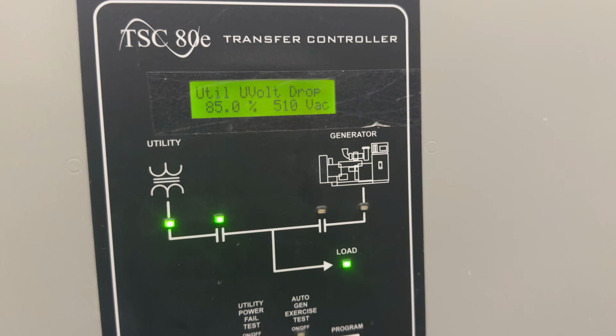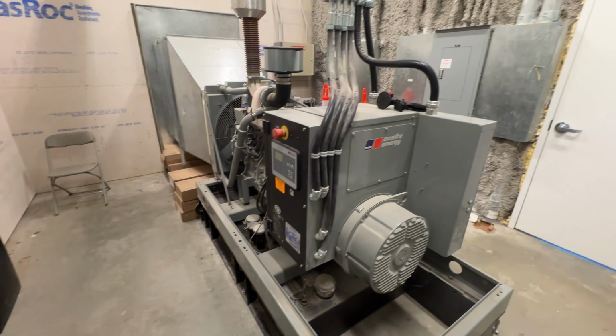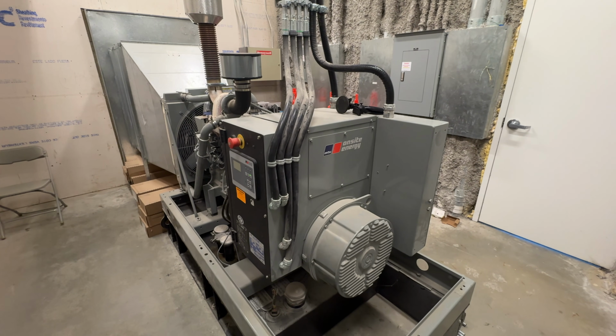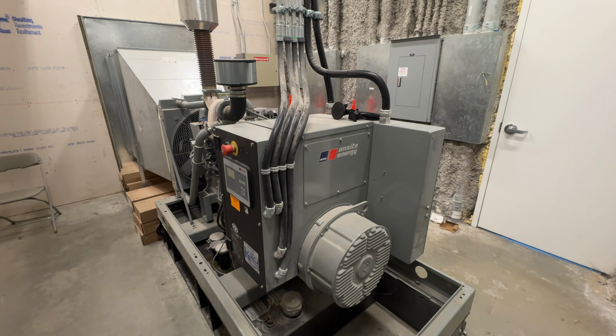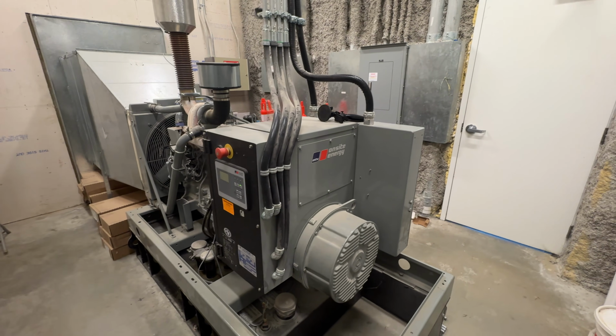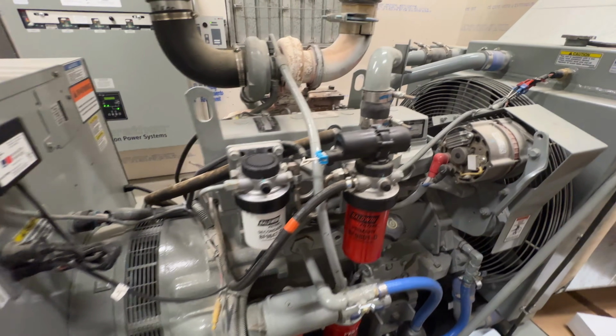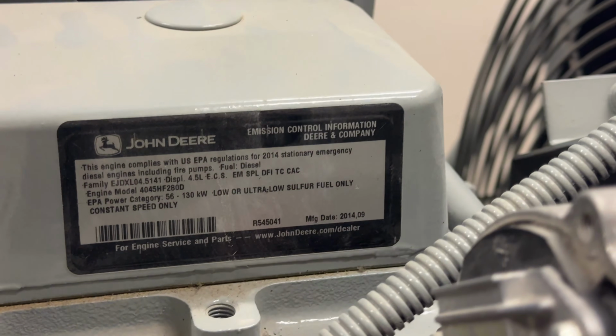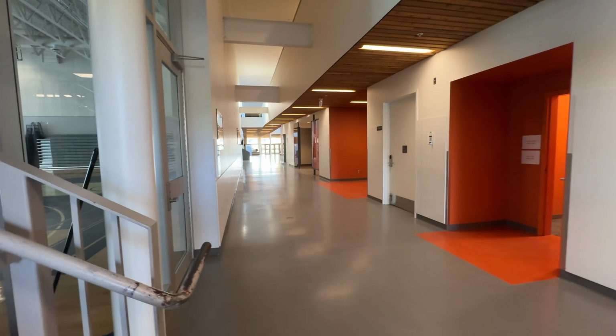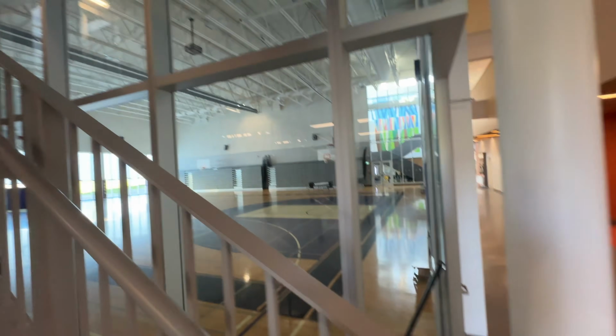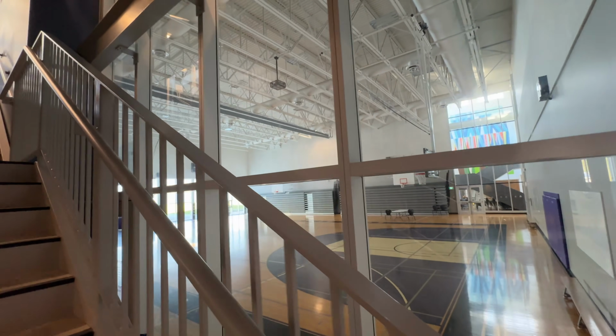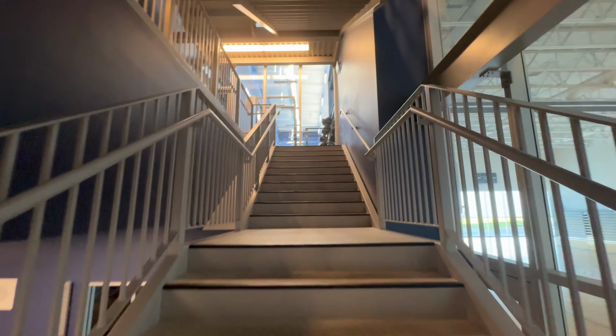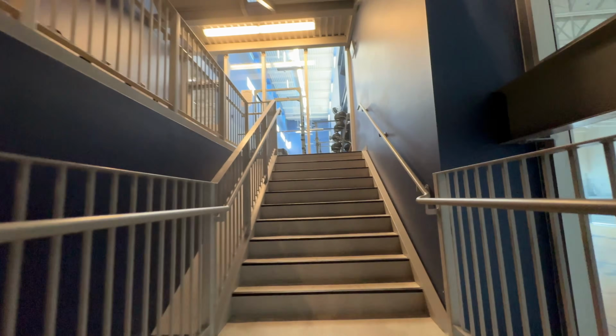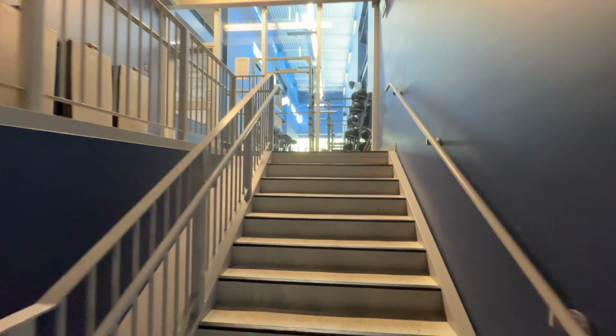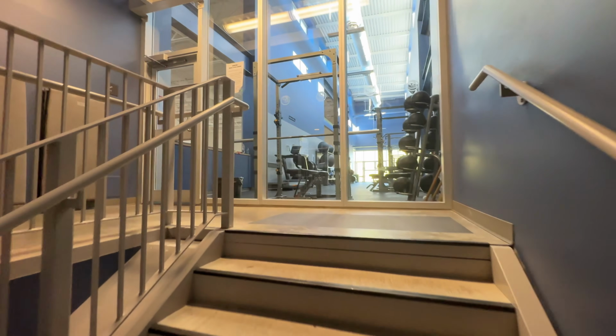And our neutral delay of 3 seconds means that while switching between power sources, it will wait 3 seconds. You need that for motors and some sensitive electronics. You don't want to be switching frequencies all of a sudden. Here on the other side of the generator, we have the engine's nameplate. So half of these corridor lights, about that, are on generator. You will have night lights in the gyms on generator, and all stairwell lighting is on generator. And then any other room with an occupancy over 60 will have some emergency lighting.